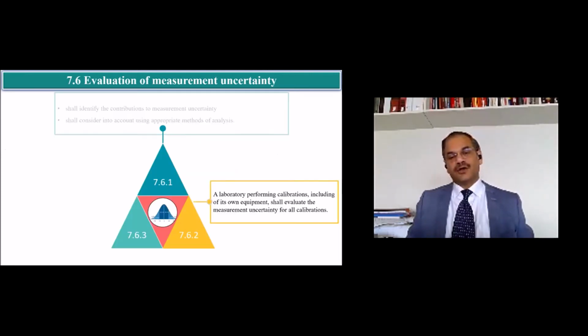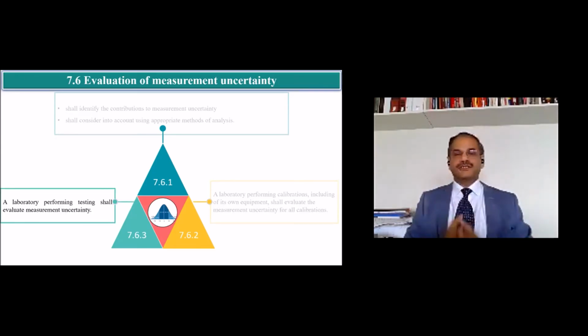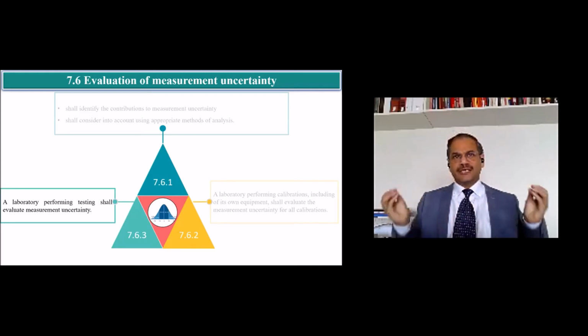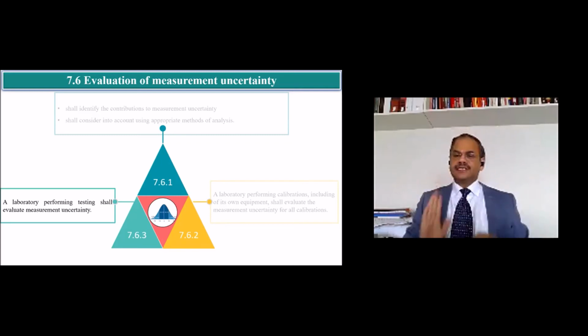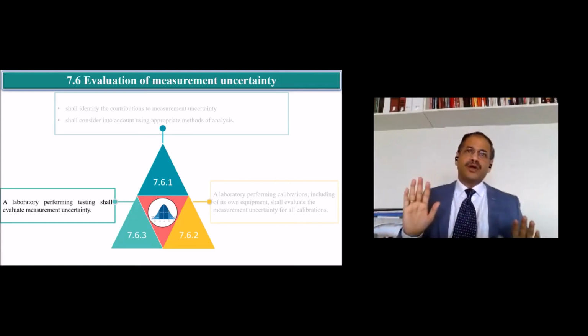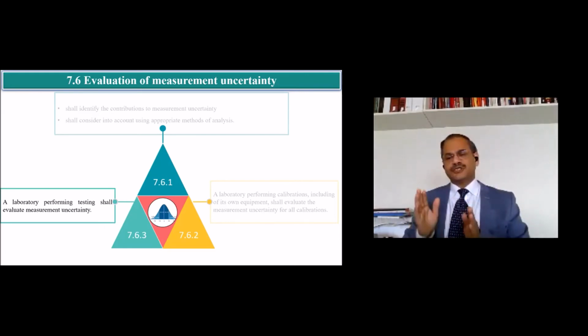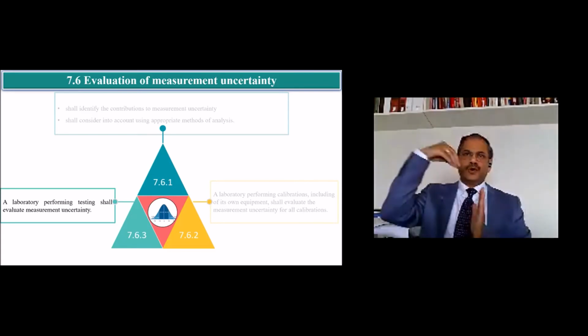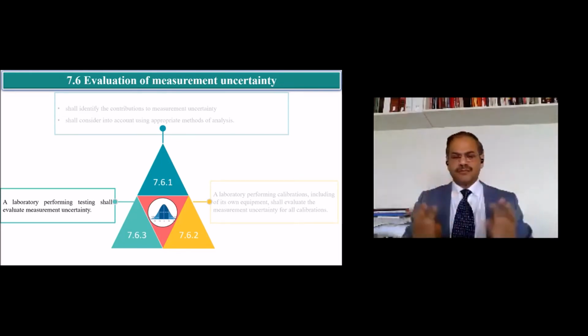Then next one is measurement uncertainty. This is a very big subject, but as per this clause, the main thing is that all the measurement uncertainty contributors have to be included while calculating uncertainty. Each lab performing test or calibration shall estimate its uncertainty for all the tests and calibrations being performed. Testing labs are a little lighter here, but a calibration lab has to be very, very clear on its calibration uncertainty, because that uncertainty percolates into your testing when you are calculating your uncertainty. So it is a very simple requirement: for all the tests or calibrations you perform, you shall estimate your measurement uncertainty, and all the uncertainty contributors have to be included. Whether to report it or not, we will see in the next chapter.